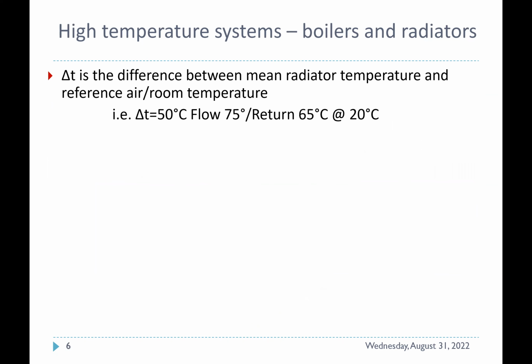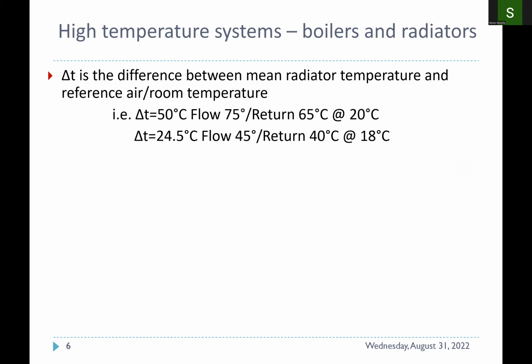So you will have, at a delta T50, flow over return of 75 over 65 degrees and a room temperature of 20. When you do that calculation, it's 50: 75 plus 65 divided by 2, minus 20. Similarly, if we do the mean between 45 and 40, which are the typical flow and return temperatures for a heat pump, air source or ground source, we always encourage using this, and you'll see later on why. You will have a delta T of 24.5 if the room temperature, for example, is 18. I'm looking at the bedroom there, or landing or hall.